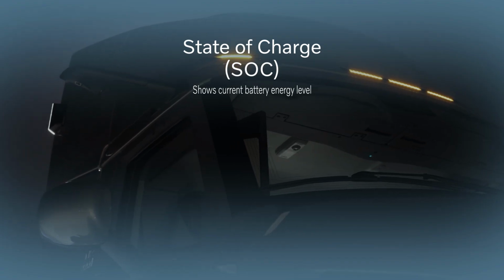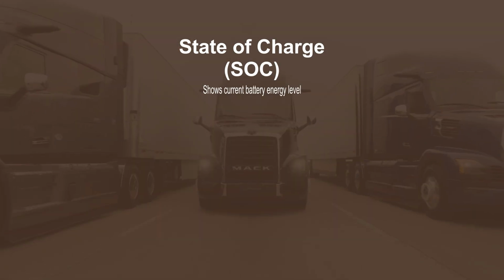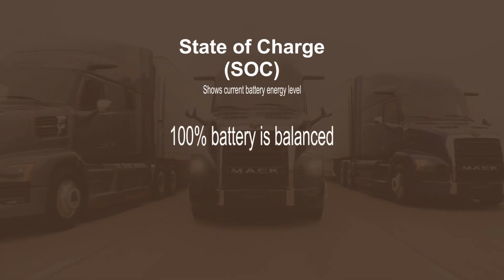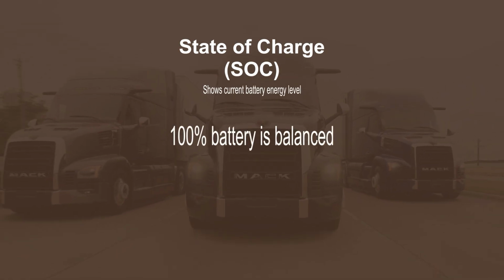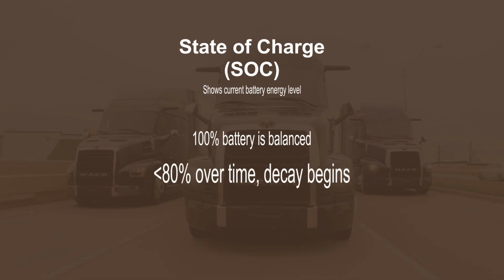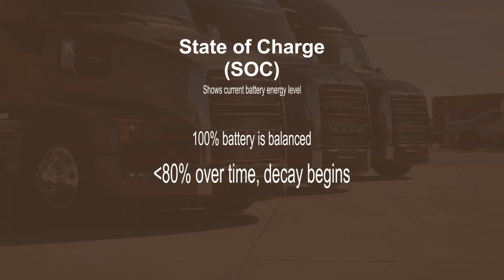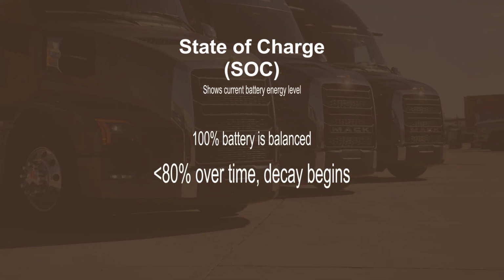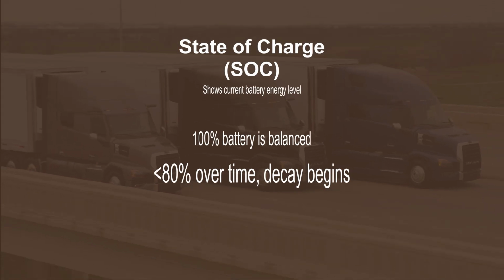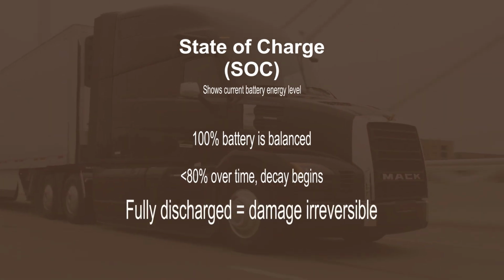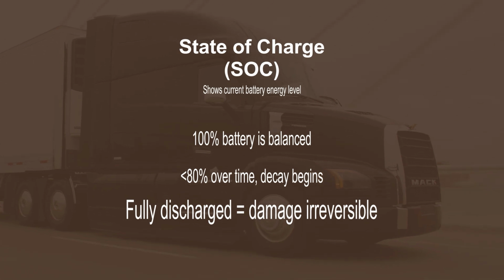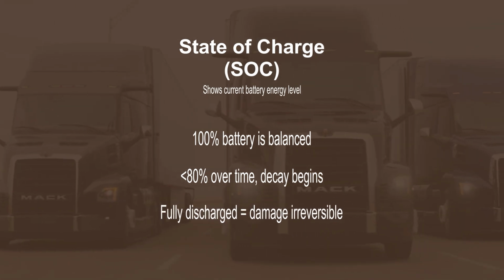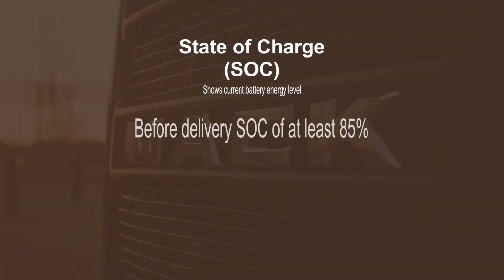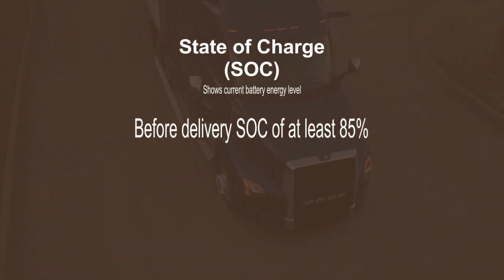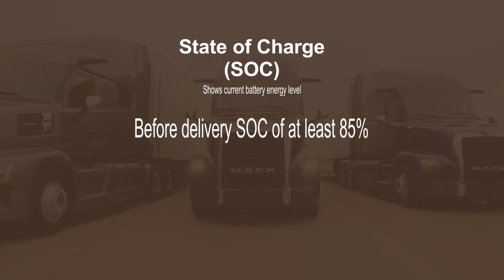State of charge, or SOC, shows how much energy the battery has available at the moment. At 100%, the chemistry inside is balanced and healthy, but if state of charge remains below 80% for too long, sulfation begins to form, which permanently reduces the battery's ability to hold a charge. If it's fully discharged, both plates convert to lead sulfate, the electrolyte turns to water, and the damage can't be reversed.